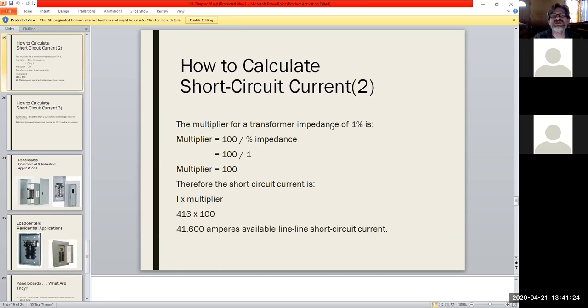But in any case, how do we calculate it? This just gives you the steps and how to go through it. Really it comes back to what the rating on the transformer is going to be. So we have the multiplier for your transformer impedance of 1%, and like I say, it is going to be really, really low. So we look at 100 divided by the percentage of impedance. In this case, as an example, they use an impedance of 1, so 100 divided by 1, of course, is 100. Then you just multiply out your current times your multiplier, right? So you figure the 100 times the 416, and that means you have 41,600 amps for line-to-line short circuit current.